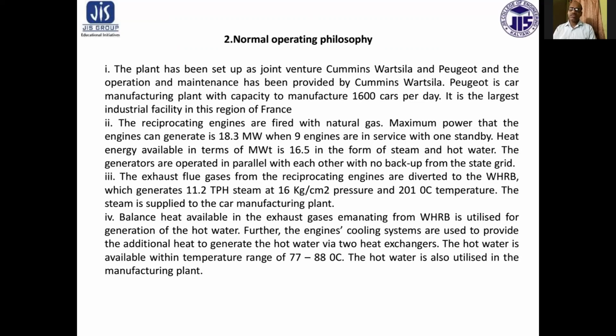The exhaust flue gas from the reciprocating engines is diverted to a waste heat recovery boiler, which generates 11.2 TPH steam at 16 bar pressure and 201 degrees centigrade temperature. The steam is supplied to the car manufacturing plant. The balance heat available in the exhaust gases from the waste heat recovery boiler is utilized for generation of hot water. Further, the engine cooling systems provide additional heat to generate hot water via 2 heat exchangers. The hot water is available within a temperature range of 77 to 88 degrees centigrade. The hot water is also utilized in the manufacturing plant.